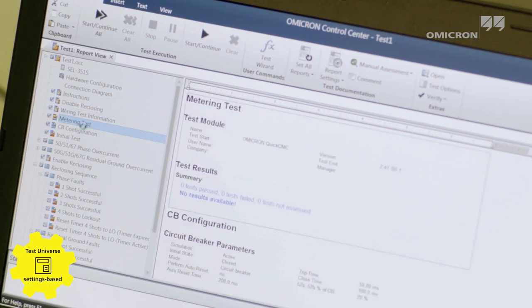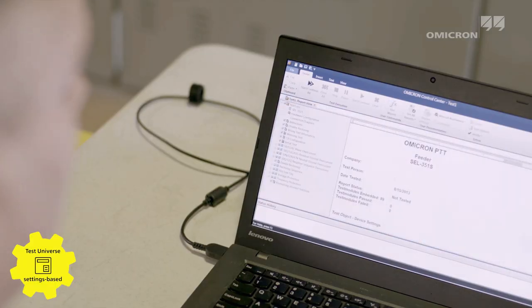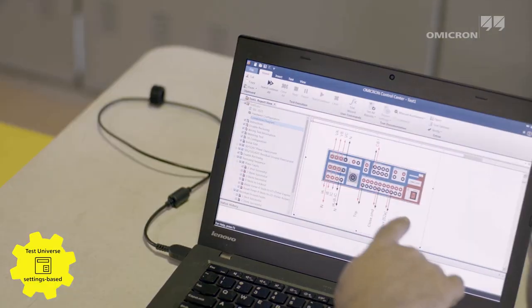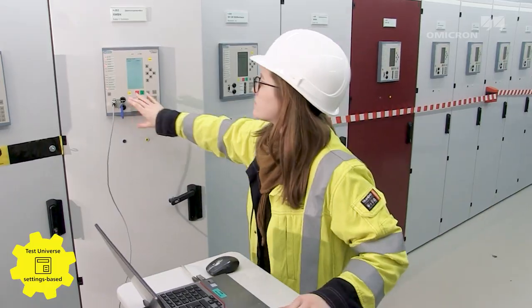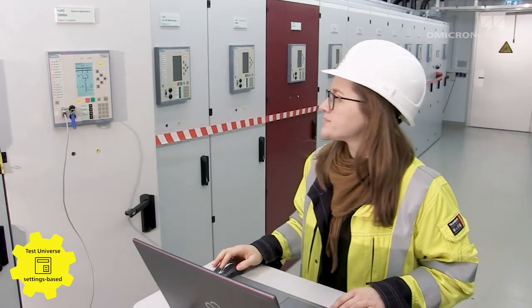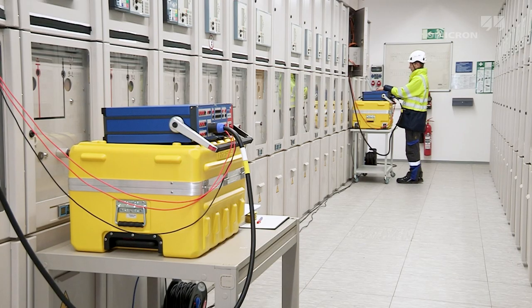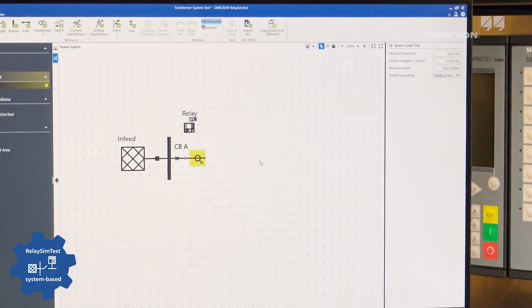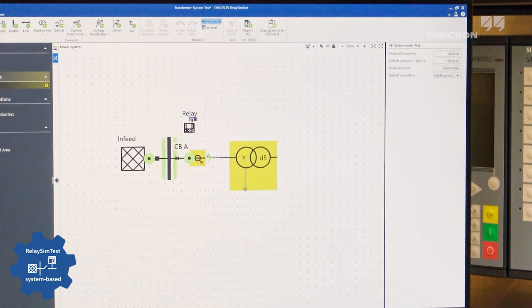Flexible test plans, arbitrarily customizable test templates for more than 400 protection relays, as well as workflow structuring, reduce testing time by up to 70%. The system-based testing approach of RelaySimTest makes it easy to test an entire protection system's functionality.